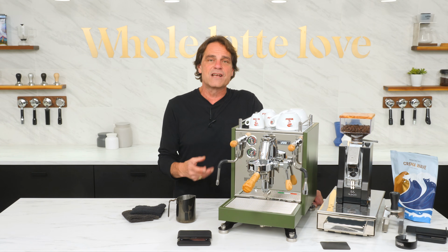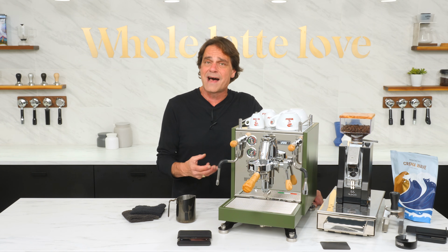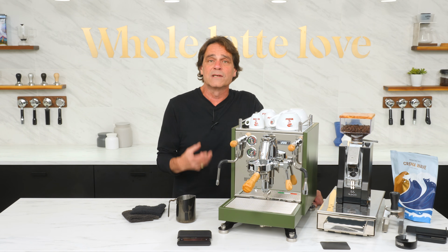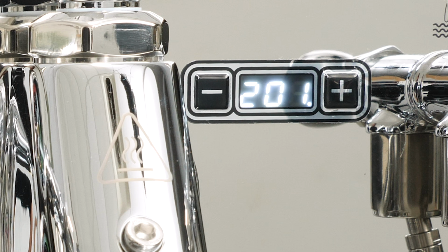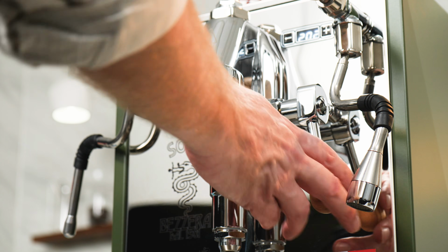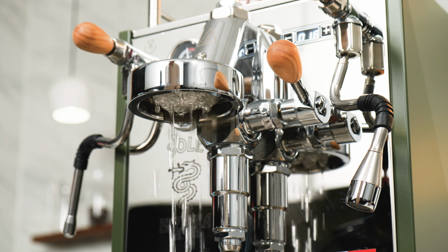Machines with heat exchange boilers generally have a sweet spot of temperature accuracy shortly after fully warming up. If they sit on and idle for long periods, temperatures generally creep up a few degrees, and you'll want to do a short flush to cool it down a bit.